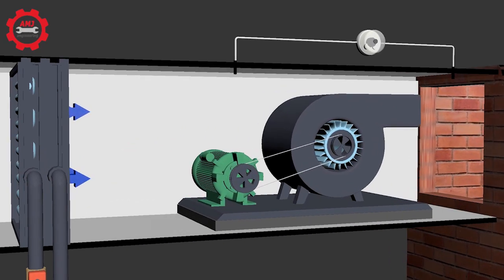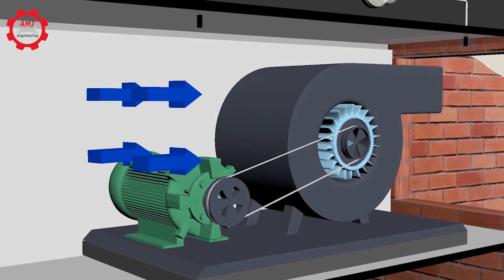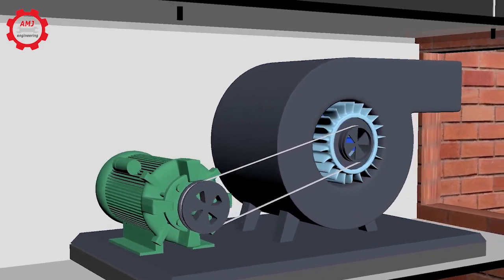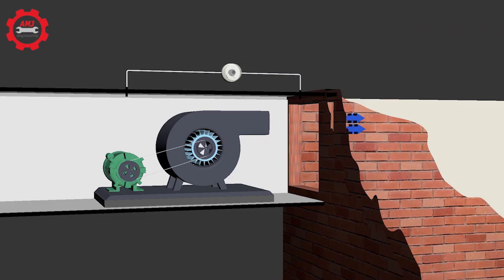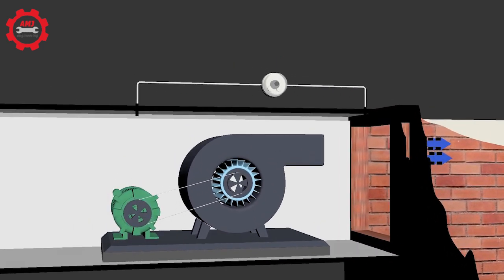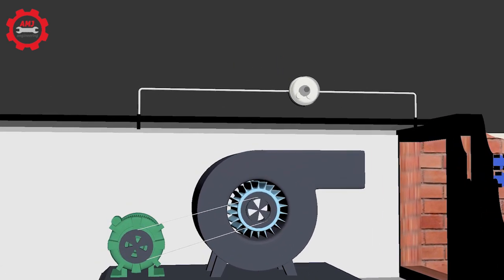The nice, cooled and non-humid air is then transferred to the space through the fan to create a comfortable environment. The speed of this fan is controlled from the space thermostat by simply increasing or decreasing the fan speed. Another pressure differential transmitter could be installed along the fan and connected to the BMS system to give an indication of a damaged belt in case of zero pressure difference.